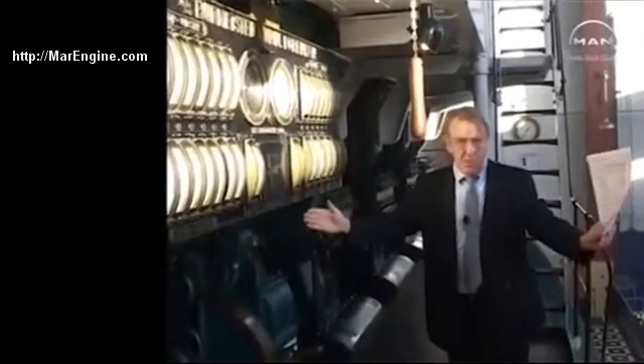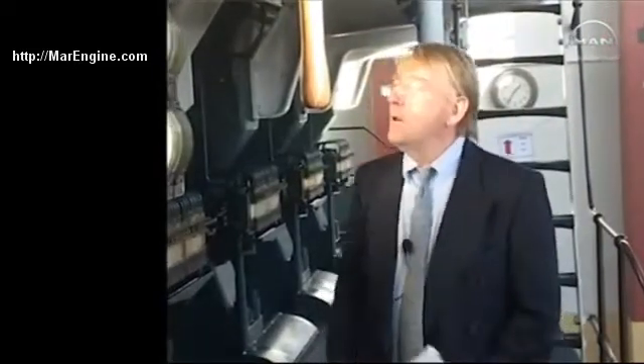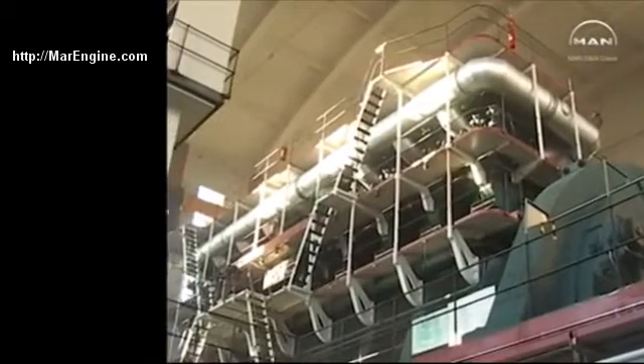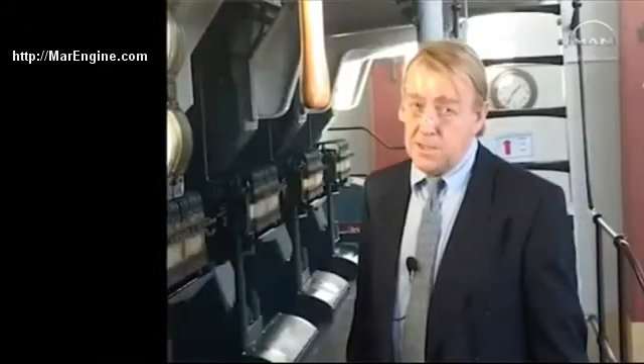The engine has eight cylinders, each with a piston diameter of 840 millimeters. The stroke of each piston is 1,500 millimeters — that's a little less than my height. This engine is actually a double-acting diesel engine, which is not used anymore. But that was the only way to boost power in the old days. Nowadays, on modern engines, an engine of this size would have a power which is three or even four times higher, by using an air supply system with a turbocharger.